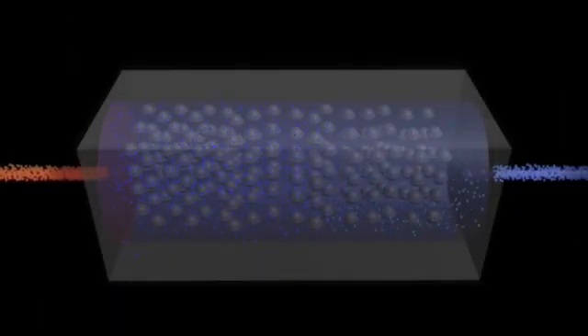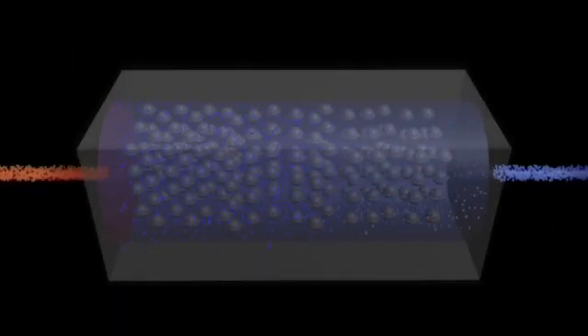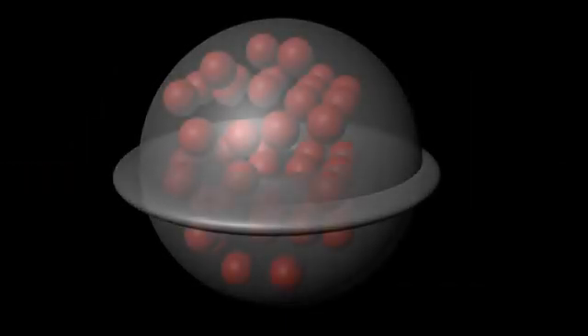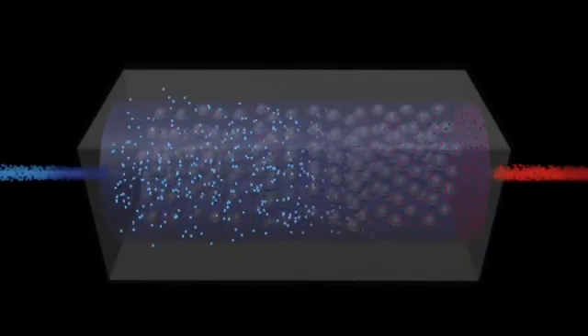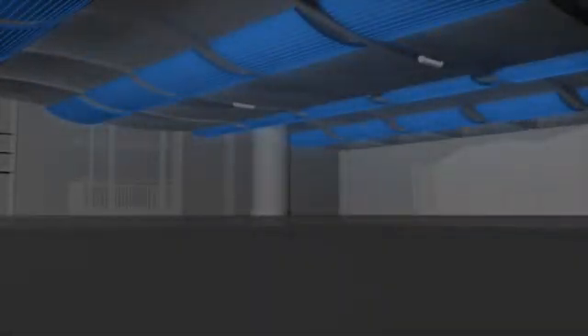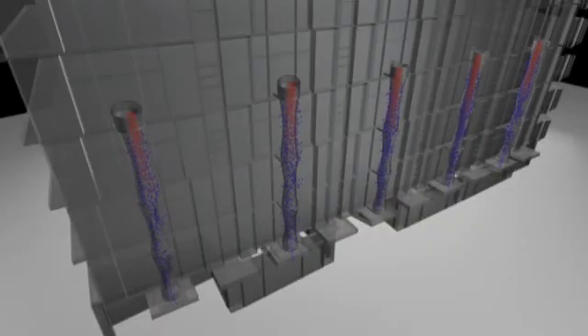The cold water is used to cool down thousands of metal balls containing phase-change material that can freeze at 15 degrees. These balls act like a battery for cooling energy and are used to cool down water that is then pumped into chilled beams and chilled ceiling panels. This water can then be re-cooled and re-used.